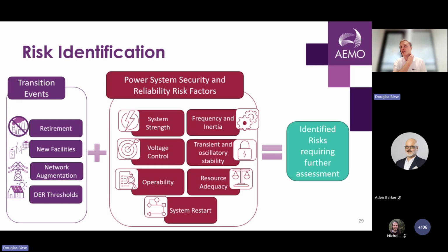We then combine that with an assessment structured around a set of power system security and reliability risk factors. That's system strength, frequency and inertia, voltage control, transient and oscillatory stability, operability, which is the complexity that we have to operate within to manage the power system, resource adequacy and system restart. There's quite a wide range that we're assessing under this, but there's a structured assessment that we carry out on these pieces, and where the combination of an event and that assessment of risk under one of those factors is identified, that's where we view that a further assessment is required. It's the combination of event and risk factor.